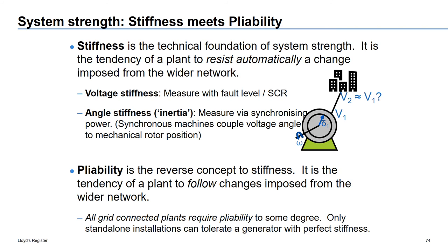Now, the complementary concept of stiffness is pliability, which is really just the tendency of equipment to follow changes imposed from the wider network. The important thing here is that all equipment in grid-connected systems needs a degree of pliability, because it's always necessary at some point to move an entire power system from one operating point to another. And in order for that to happen, every piece of equipment in that power system needs to be able to follow that change to some extent. So it's a delicate balancing act between these two principles.